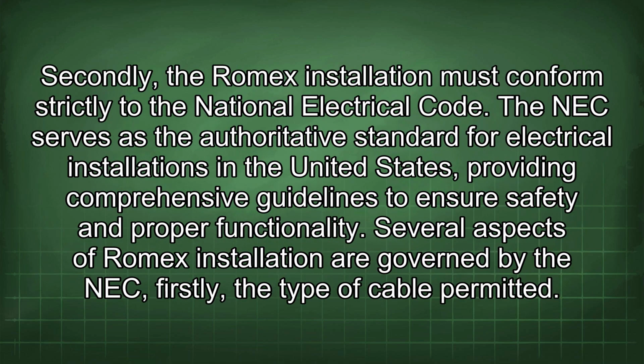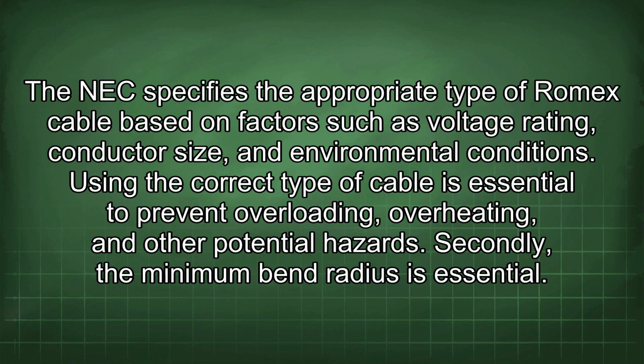Secondly, the Romex installation must conform strictly to the National Electrical Code. The NEC serves as the authoritative standard for electrical installations in the United States, providing comprehensive guidelines to ensure safety and proper functionality. Several aspects of Romex installation are governed by the NEC. Firstly, the type of cable permitted. The NEC specifies the appropriate type of Romex cable based on factors such as voltage rating, conductor size, and environmental conditions. Using the correct type of cable is essential to prevent overloading, overheating, and other potential hazards.